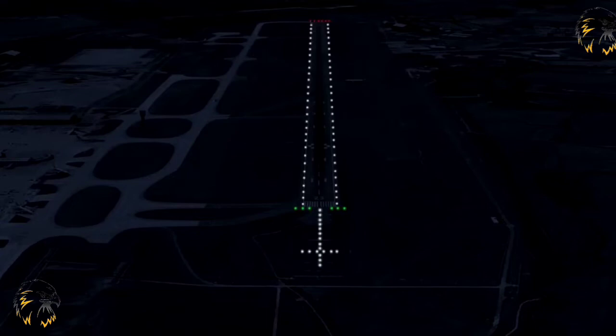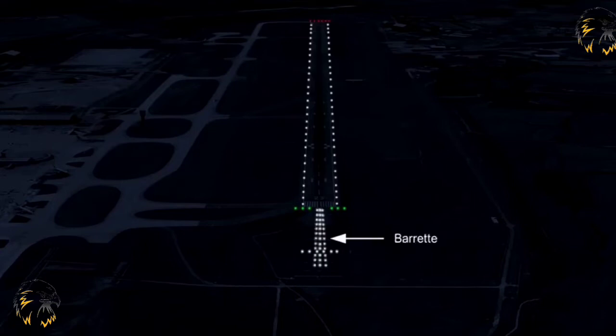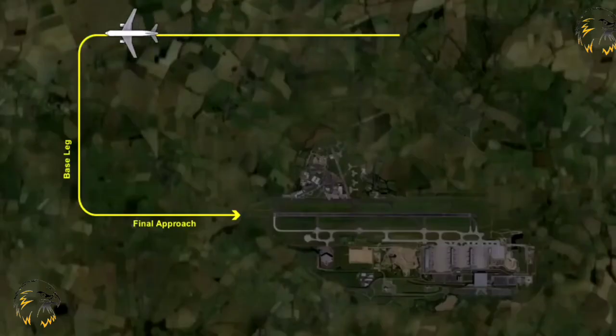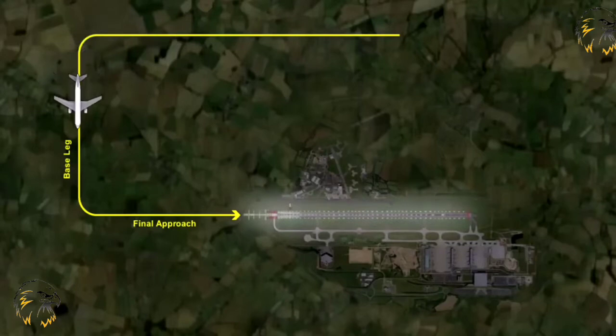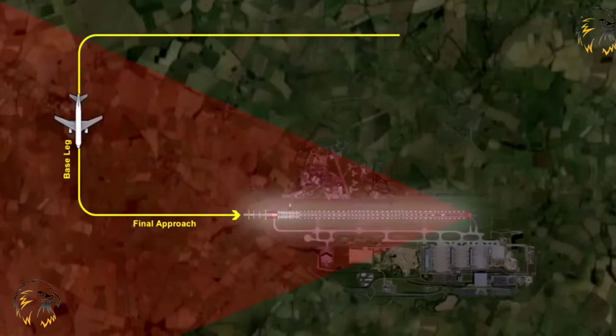An example is shown here. The lights in this system are fixed and normally coloured white. Each centreline light shall consist of either a single source light or a barrette of at least 3 metres in length. On a non-instrument runway, the lights should show at all angles in azimuth for a pilot on base leg and final approach. The intensity of the lights should be adequate for all conditions of visibility and ambient light.